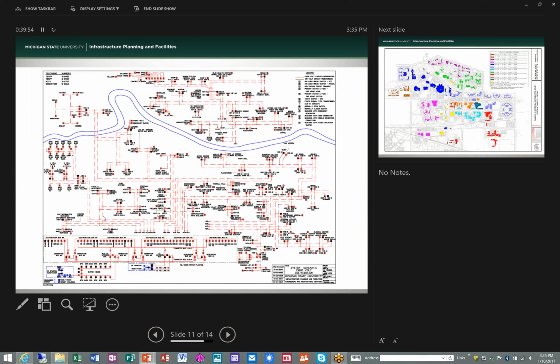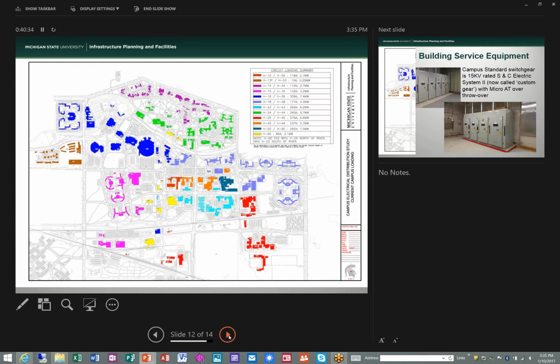Well, when we talk about the circuit pairs, I'll use bus 1 and bus 3 as an example. We have a breaker, and most recently I'll use circuits 10 and 30 as an example. So circuits 10 and 30 feed the new engineering chiller, right? And so we got a breaker on bus 1 for circuit 10, and the same thing, a breaker for circuit 30, and those feed out. And then the tie that you're referring to happens in that 15 kV gear lineup inside the building.